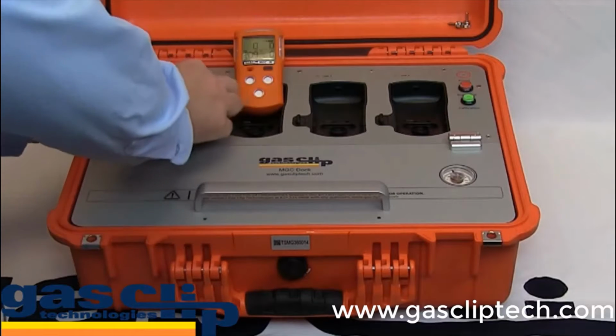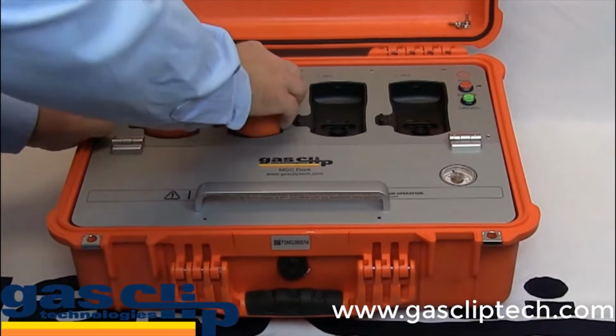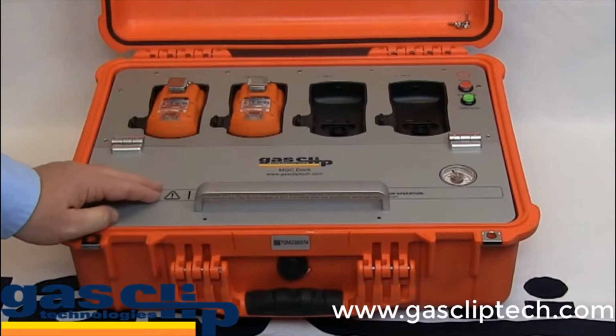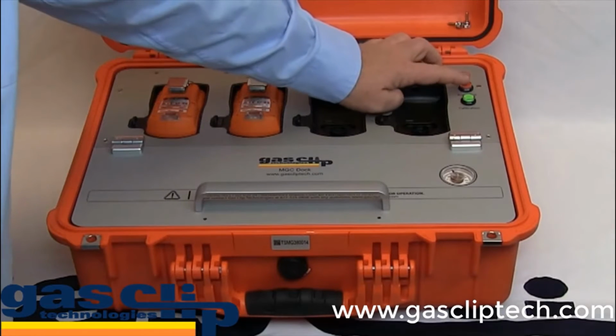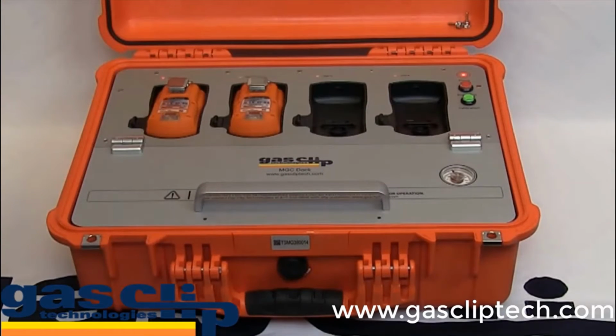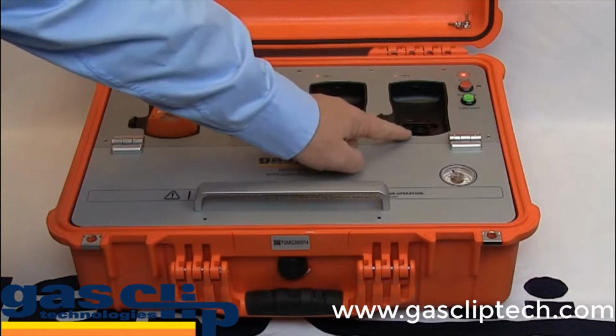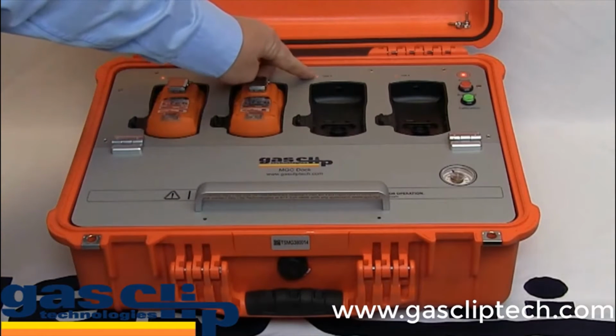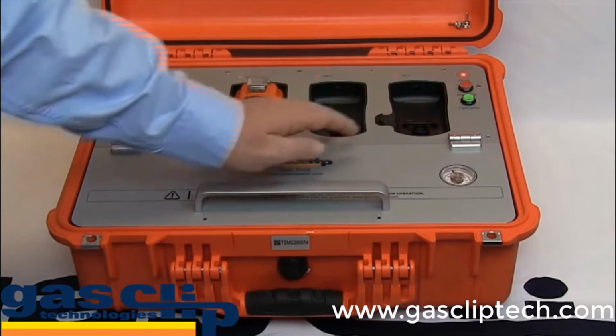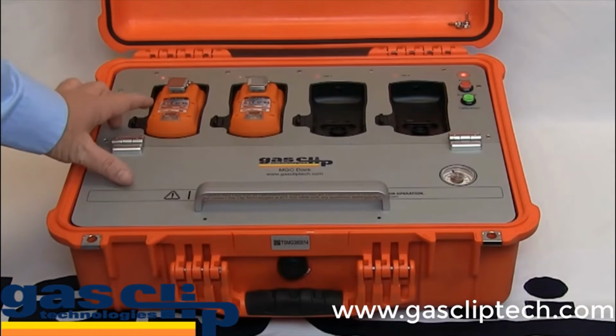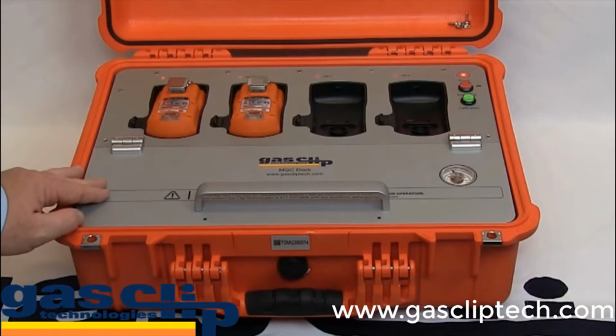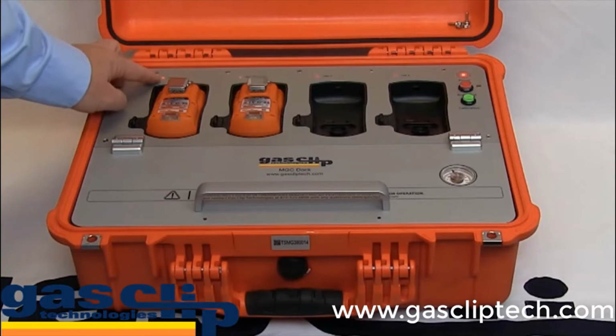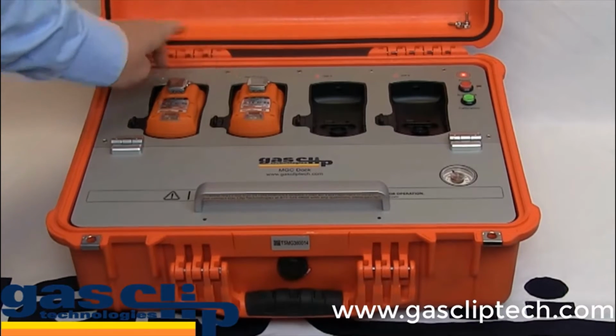Simply place your monitors face down in the bays and choose the appropriate test you wish to perform. We will perform a bump test. You will hear 2 beeps because there are 2 monitors in the first 2 bays. Since there are no monitors in the last 2 bays, the lights above will go red and these will be disabled for this test. Gas is now being applied to the monitors for approximately 15 to 18 seconds. Once the monitors have passed the test, the light above the associated monitor will go green, like so.